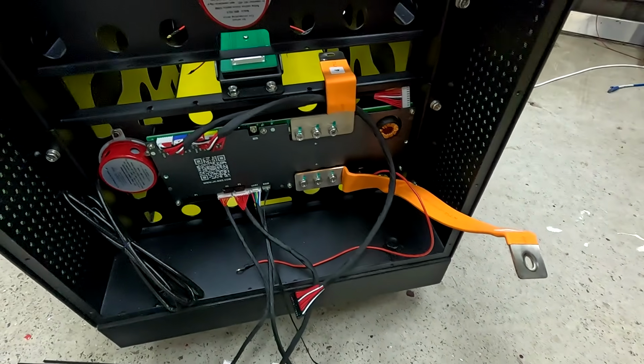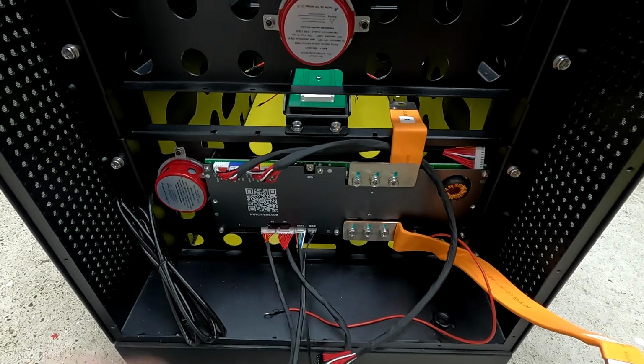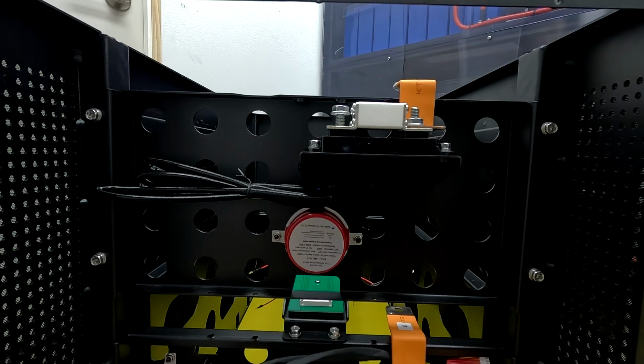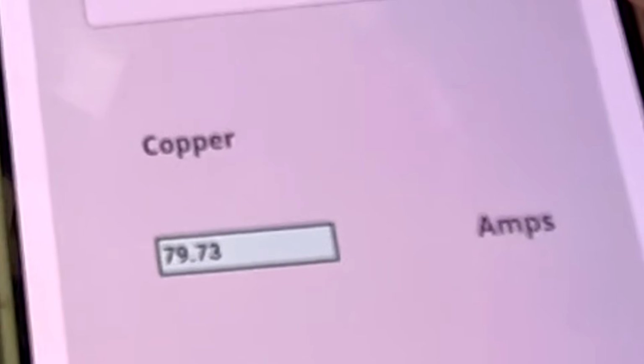That's the maximum current allowed for this size of bus bar. So we have a 300 amp BMS in here with a 300 amp fuse and a 300 amp circuit breaker, but the bus bar is only rated for about 80 amps.